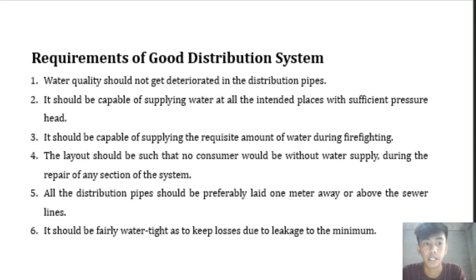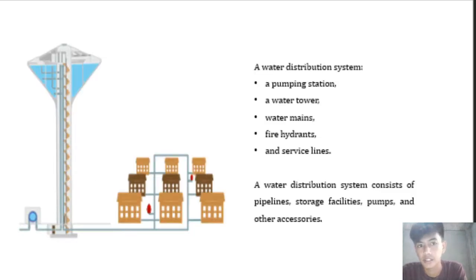The layout should be such that no consumer would be without water supply during the repair of any section of the system. All distribution pipes should preferably be laid one meter away from or above the sewer lines. Lastly, the system should be fairly watertight so as to keep losses due to leakage to a minimum.